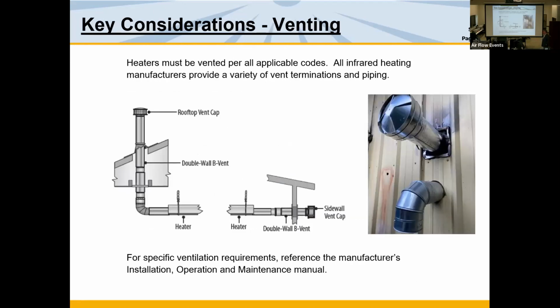Next slide. Okay, venting the heaters. This is where people don't understand what they need to do. If you look closely at that picture on the right, that's what I went to Montana for this week. Instead of venting with the thimble and the double wall vent pipe and the whole thing that we have depicted with the proper pieces, they bought a plumbing apparatus that sealed it. And guess what the plumbing through the wall shield was? It was rubber. You can see the rubber right here around it.